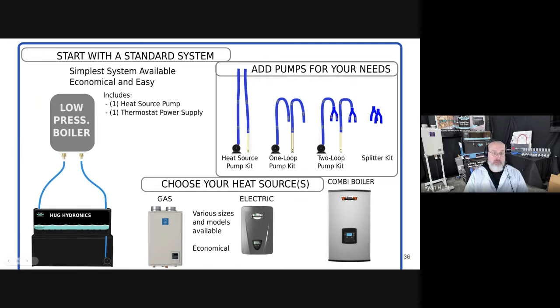Okay, this is how you think about the system. You start with the standard system, which just has the pump to feed the heat source. It's got the tank of water, the controls are there and ready to go. Then you add the pumps you need for your system. Do you need an additional heat source pump? Because we can do up to three heat sources in one tank. Do you need one-loop pumps, two-loop pumps? And then we have a splitter kit later on, in case you want to take your one-loop pump and actually feed another loop with it for some reason. So, one-loop pumps, two-loop pumps, and heat source pumps. And then you choose your heat sources. You can choose a gas boiler, electric boiler, combi boiler. If you've got your own system with a wood boiler, we can work with that.